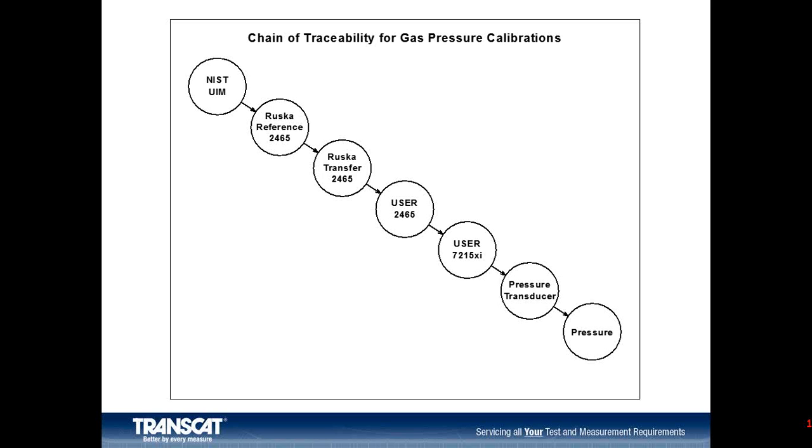In the modern terminology, we don't think of it as traceable to NIST. We describe it as traceable to the SI being the International System of Units, actually maintained in France. So we say it's traceable to the SI through NIST, typically through NIST, not essential to be traceable through NIST, but commonly it is the case.